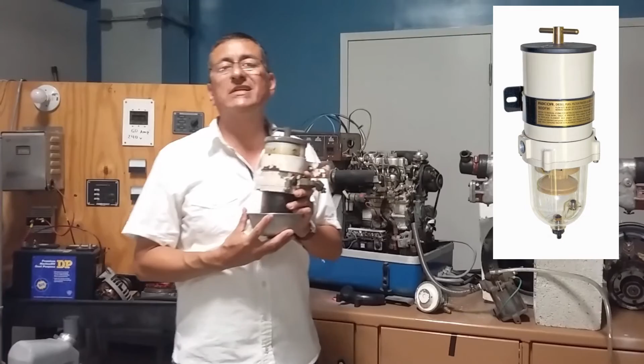And if, because the only possibility is over the water line, you need to install an electric raw water pump in series in between the strainer and the raw water pump, in order to lift the water and bring it to the raw water pump when the generator starts. Very, very important.